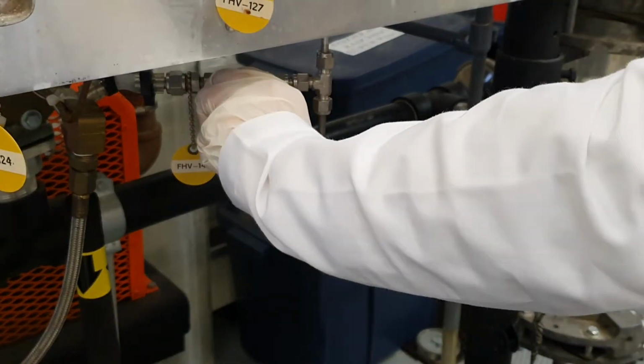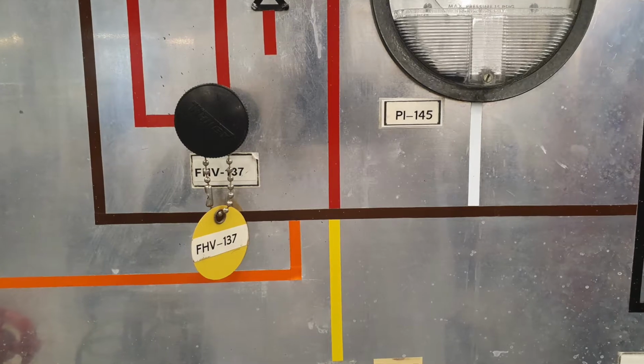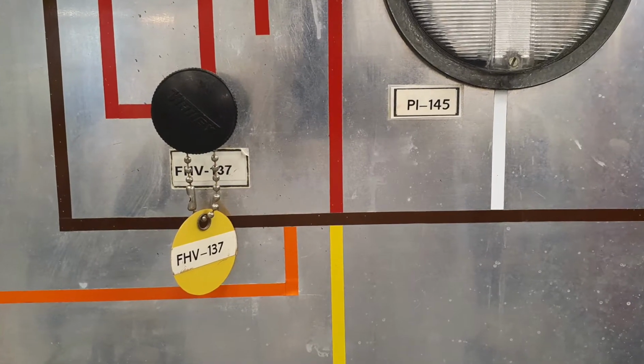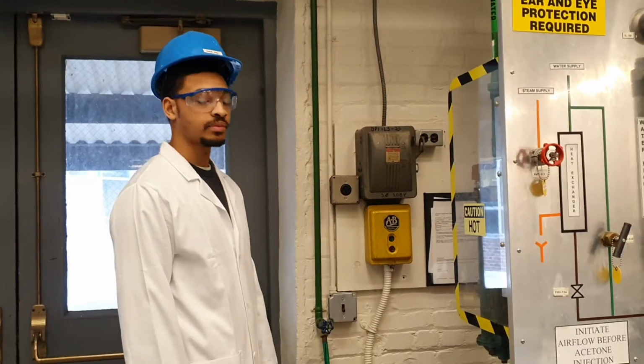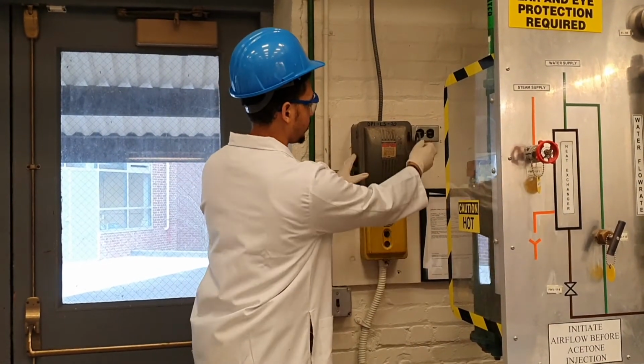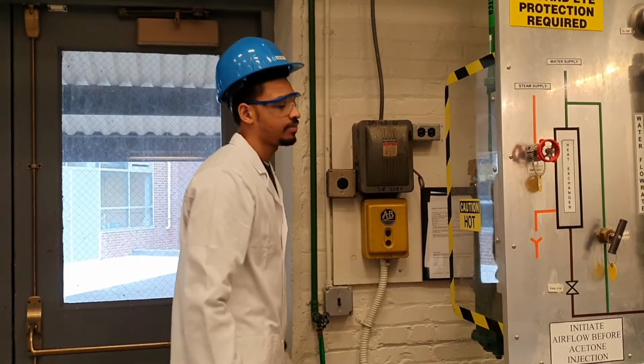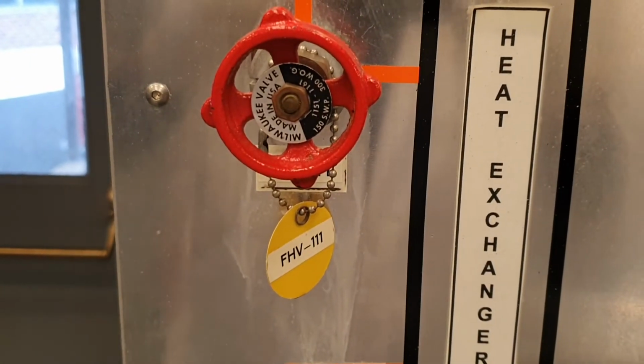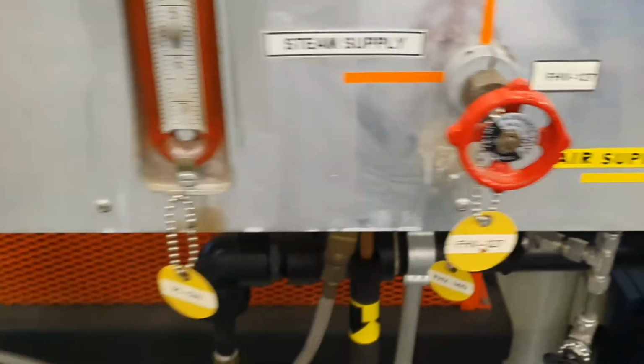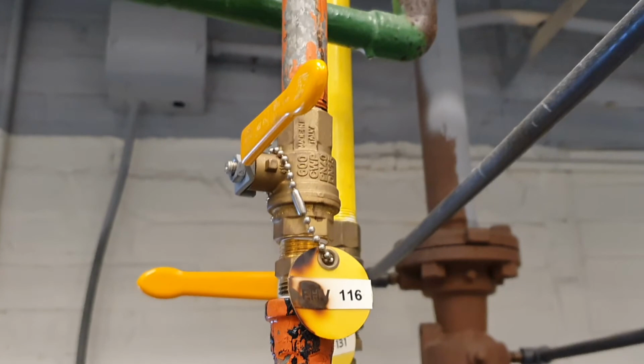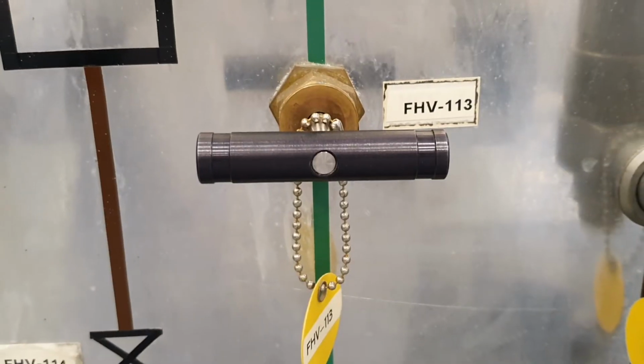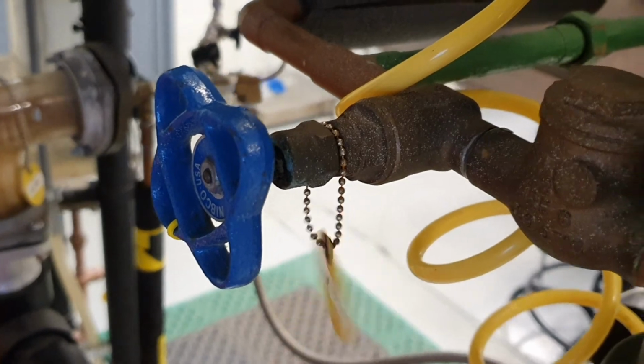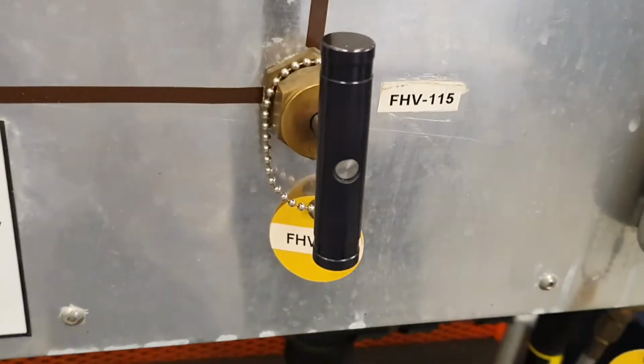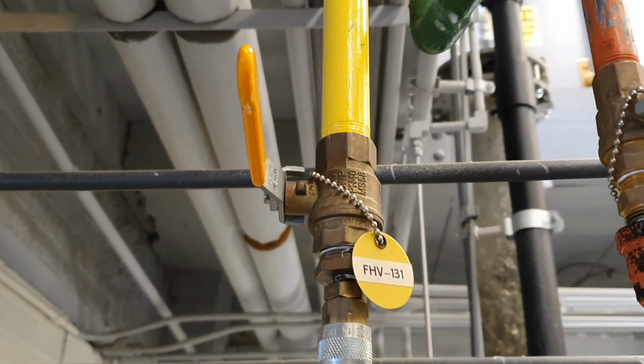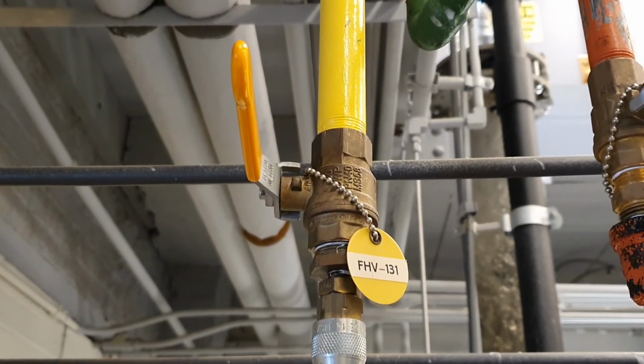To begin the shutdown procedure for the gas absorber, start by closing FHV 140 and adjust FHV 137 until FI 138 reads 0 to stop acetone from flowing into the system. Press the stop button on box S2 and pull down the lever on box S1 to turn off the air compressor. To stop the flow of steam, close valves FHV 111, FHV 127, and FHV 116. Then, close valves FHV 112, FHV 113, FHV 114, and FHV 115 to stop the flow of water into the system. Close valve FHV 131 to stop the flow of compressed air.